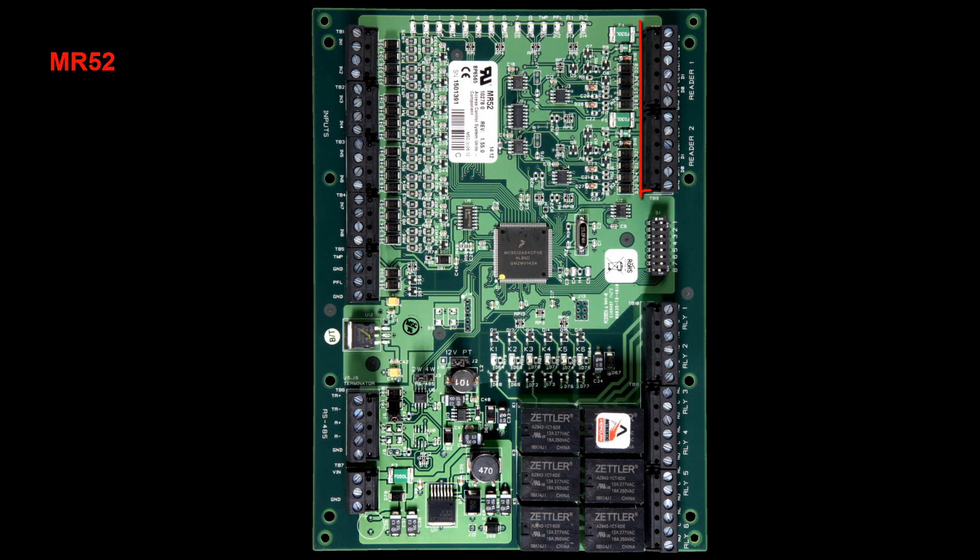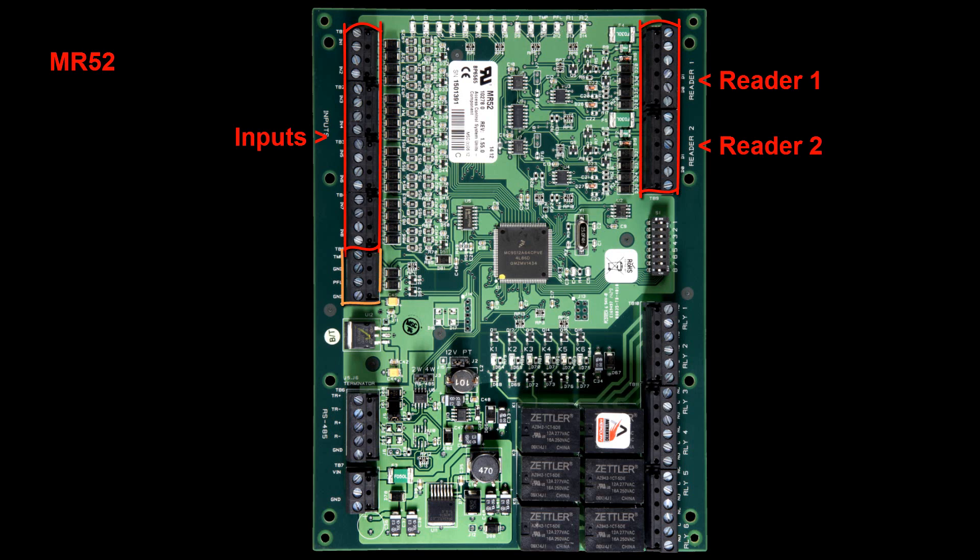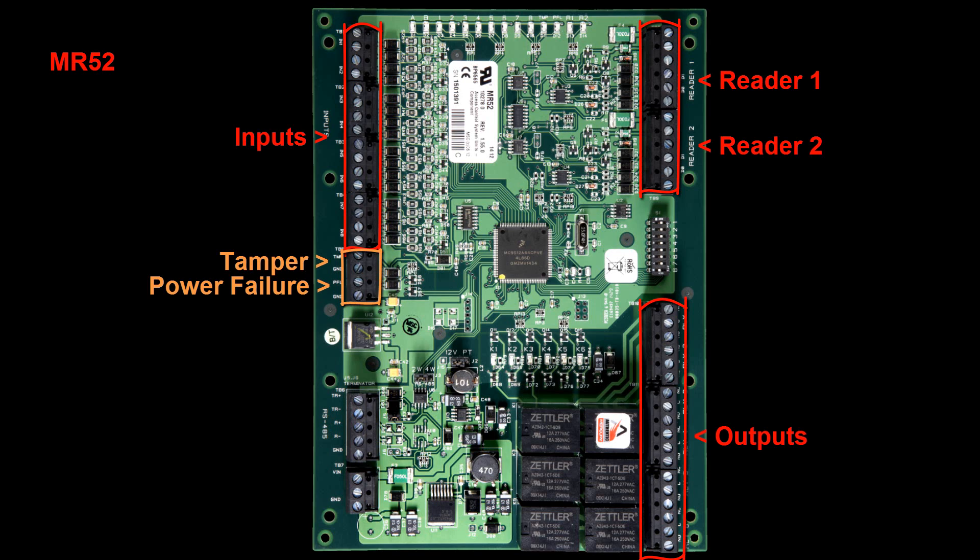The MR52 is a two-reader sub-panel with eight normal inputs, two inputs for tamper and power failure and six outputs. The MR52 communicates with the intelligent Mercury EP panel through the RS485 port using the TR+, TR-, and ground. It is powered through the voltage in and ground terminals.